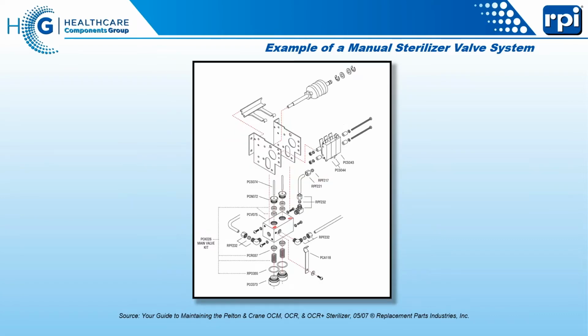Then somebody got creative and came up with this - the valve system to a Pelton Crane Omniclave, a unique bit of engineering. What we have here are 2 valves built into a manifold. Those valves are controlled by a cam, so somebody has to turn this cam to move the device from one step of the process to the next - filling, sterilization, venting, that sort of thing.